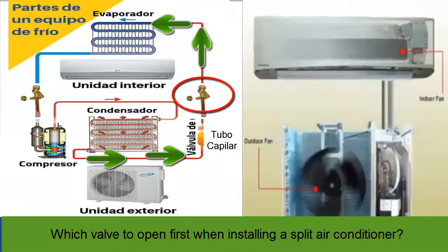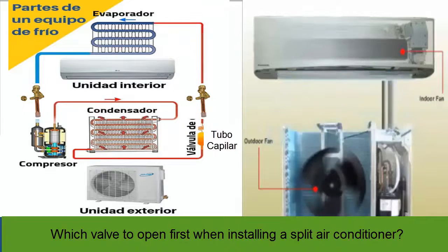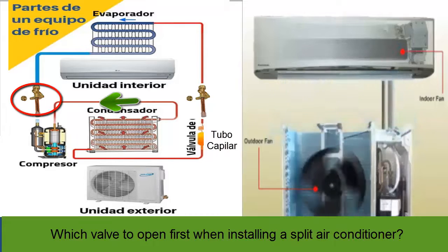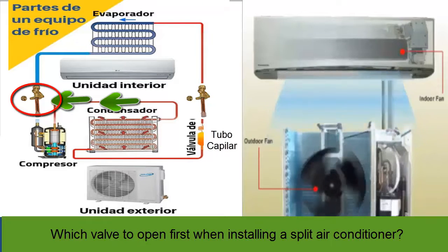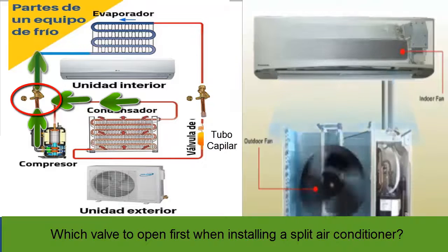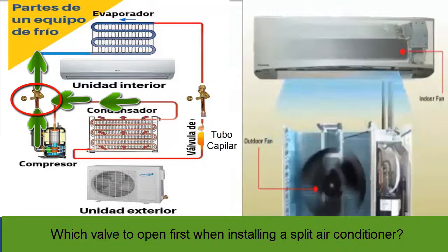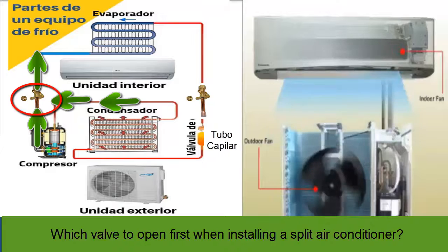In contrast, when the valve of the thicker pipe is opened first, the refrigerant may suddenly drag part of the lubricant oil located in the compressor crankcase and deposit it in the evaporator. This occurs because the exit of refrigerant through the thicker pipe or larger valve is not controlled by the capillary tube. So the best approach is to open the thin valve slowly first.